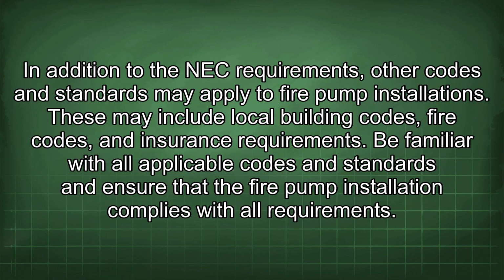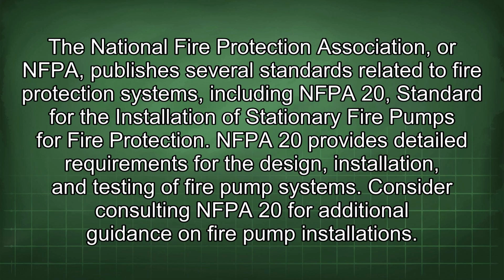In addition to the NEC requirements, other codes and standards may apply to fire pump installations. These may include local building codes, fire codes, and insurance requirements. Be familiar with all applicable codes and standards and ensure that the fire pump installation complies with all requirements. The National Fire Protection Association, or NFPA, publishes several standards related to fire protection systems, including NFPA 20, standard for the installation of stationary fire pumps for fire protection. NFPA 20 provides detailed requirements for the design, installation, and testing of fire pump systems. Consider consulting NFPA 20 for additional guidance on fire pump installations.